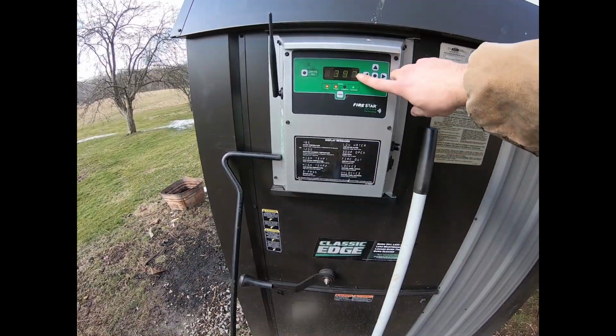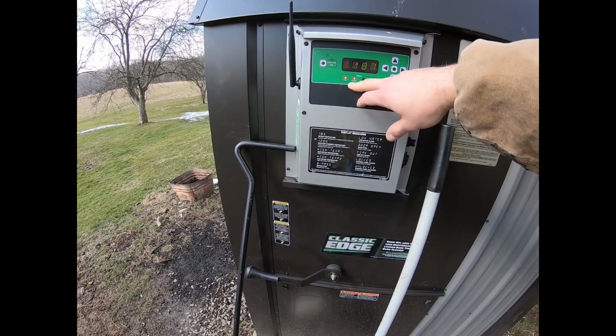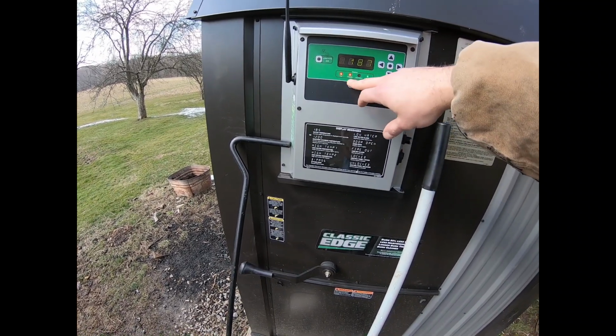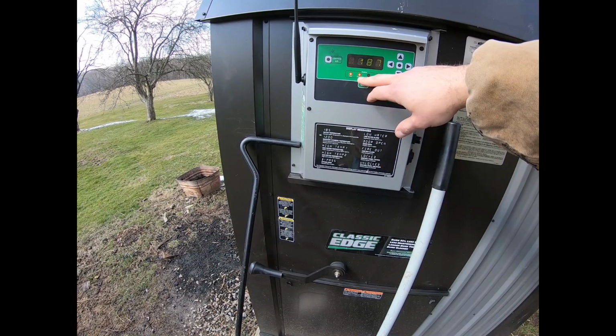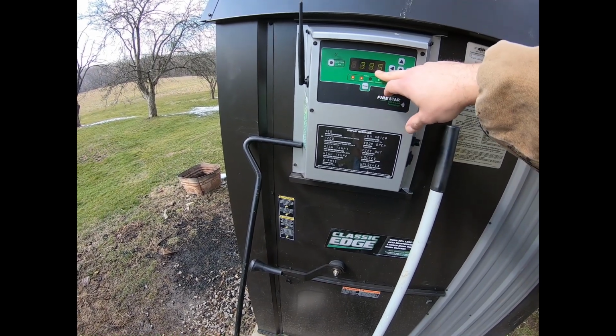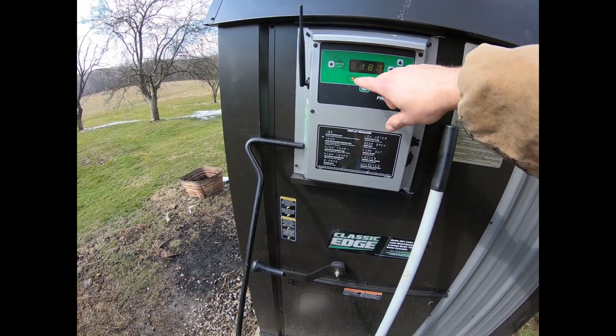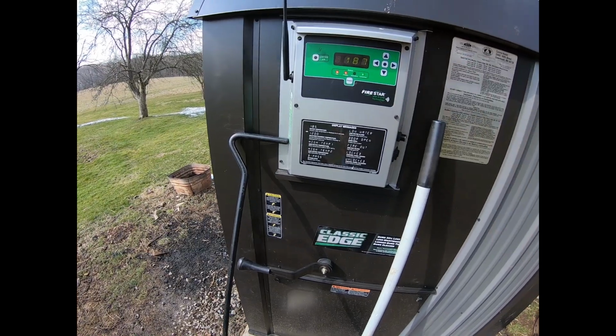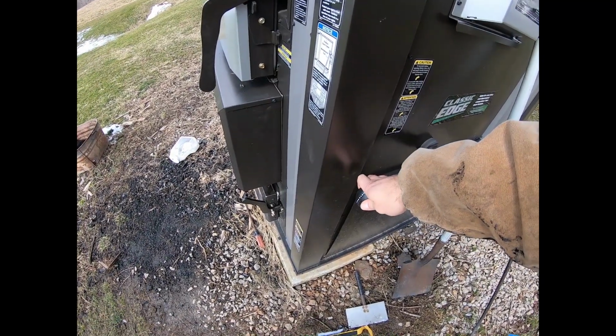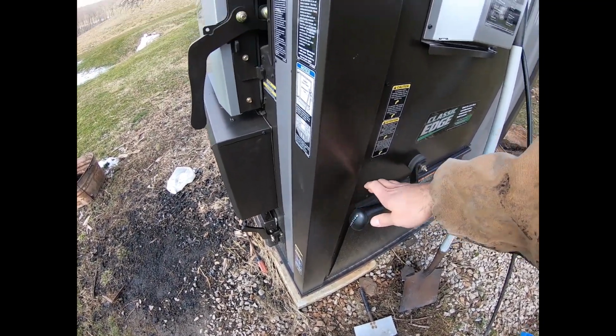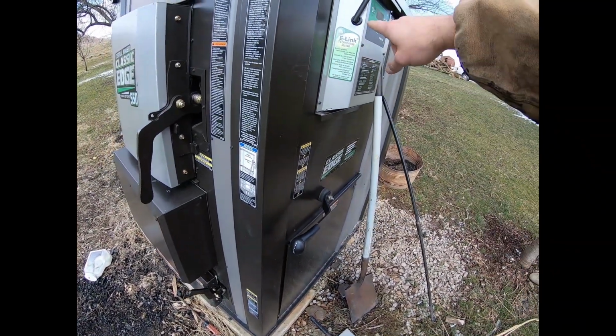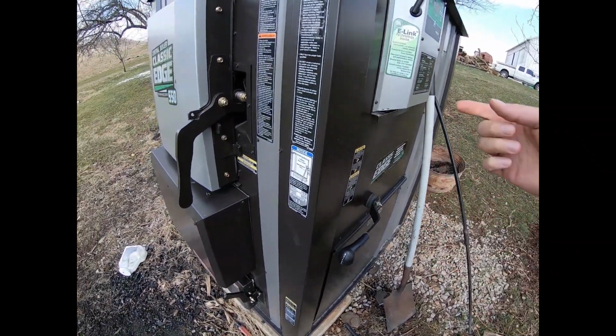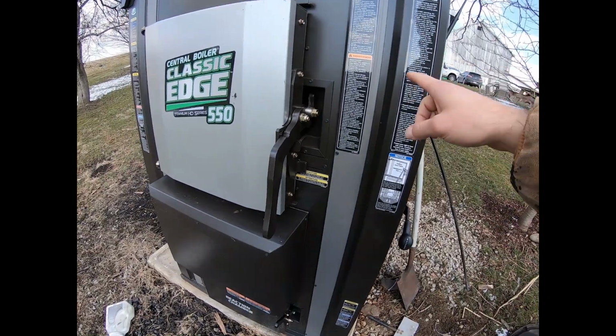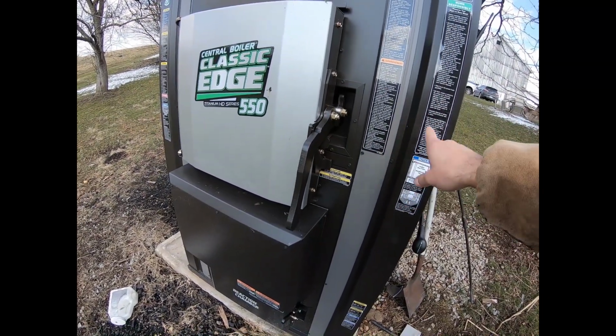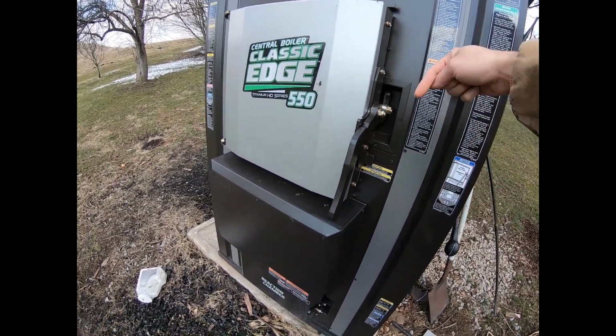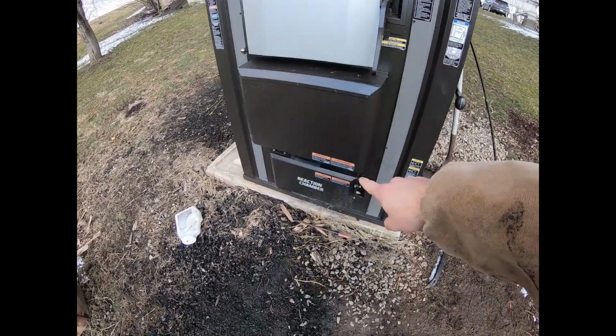So what you have here, actually the blower just kicked on. You can see by the fan's on and the primary air solenoid is open. What you got here is the reaction chamber temperature, and then the water temperature. This right here is a bypass door, and what that does is it works a lever inside of the furnace, and when you close the bypass door, as the wood is combusting inside of the firebox, the gases are forced down through to the reaction chamber.